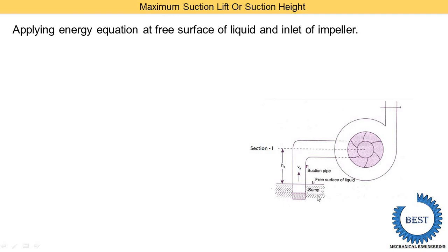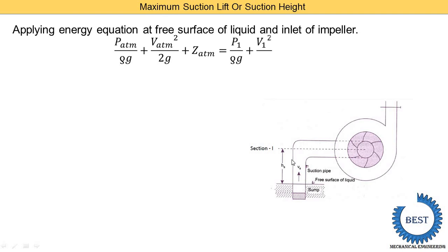At the sump level we have atmospheric conditions. Applying Bernoulli's equation: pressure energy at the sump is p_atmosphere / ρg, plus velocity energy v_atmosphere² / 2g, plus datum head z_atmosphere, equals the energy at the inlet of the impeller: p1 / ρg + v1² / 2g + z1, plus friction losses in the suction pipe hfs.